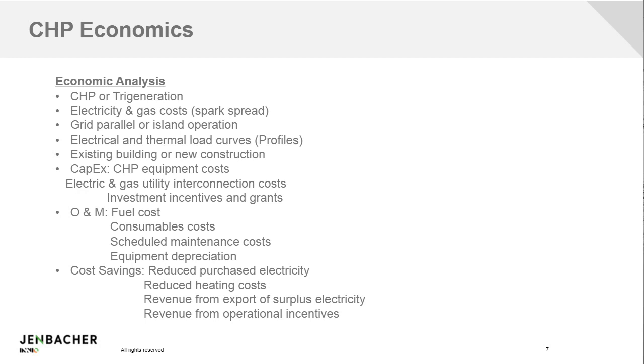Then we have to look at how we're going to run the installation. Is it grid parallel, meaning you're tied to the grid, or island operation, meaning you might disconnect from the grid? There might be reasons to do that - for example, to save costly interconnection, or if grid power is unreliable, you might disconnect completely and run on the CHP system. You might also do both: run grid parallel normally, and switch to island operation during a blackout, running your own microgrid. This increases resiliency, which is also very important for customers.